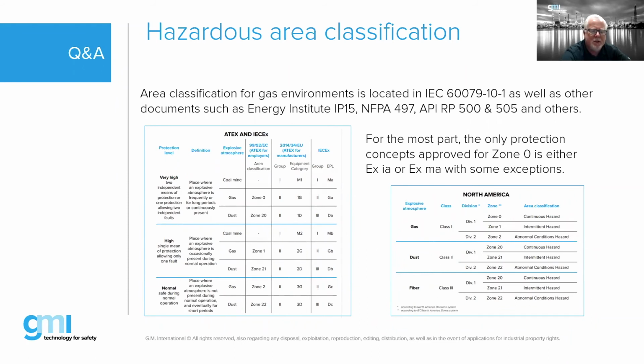And I assume it's because of the fault tolerance that you can actually achieve in building a cell phone, making it suitable for hazardous locations. So I have not seen a cell phone that's actually certified for Zone 0. I'm sure the phone manufacturers would love to have a cell phone that's suitable for inside of tanks, but I have yet to see one, and I'm assuming it has to do with the fault tolerance of a cell phone.